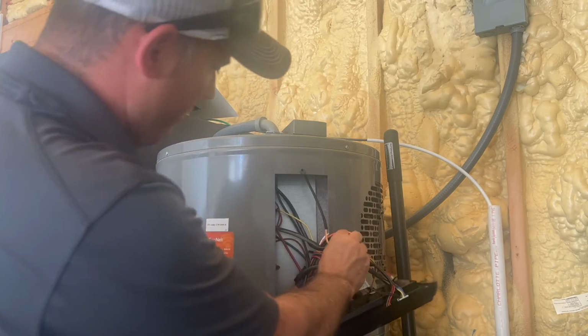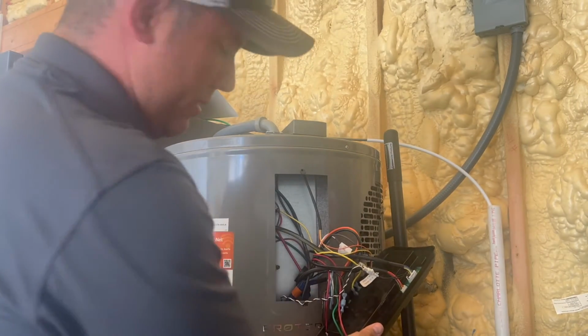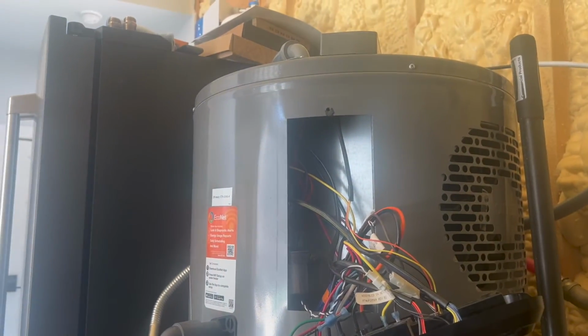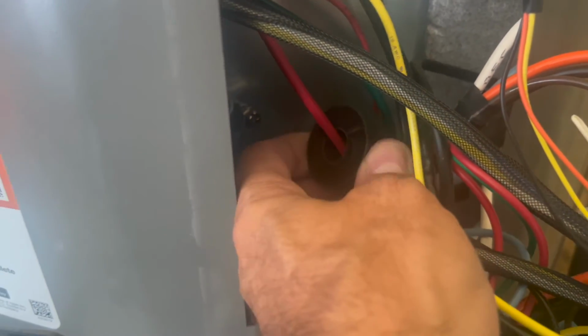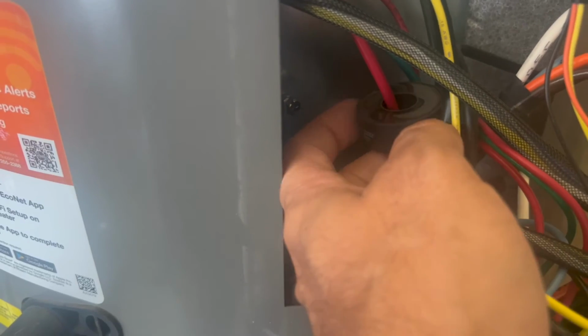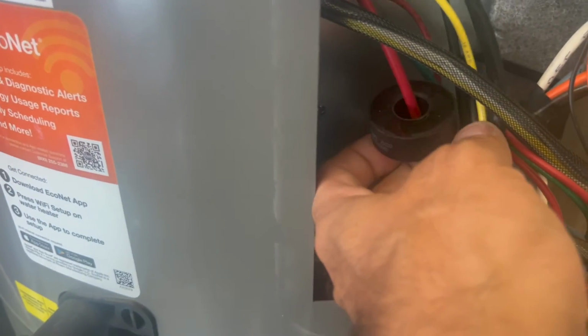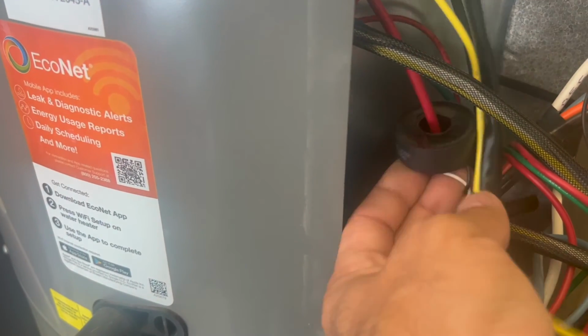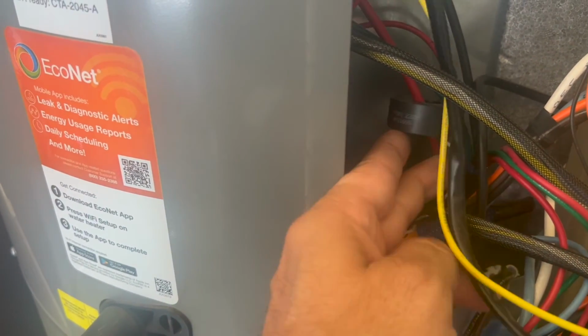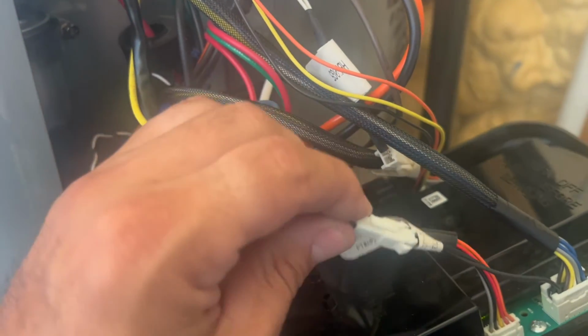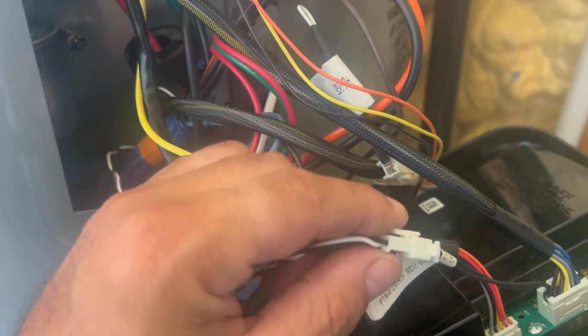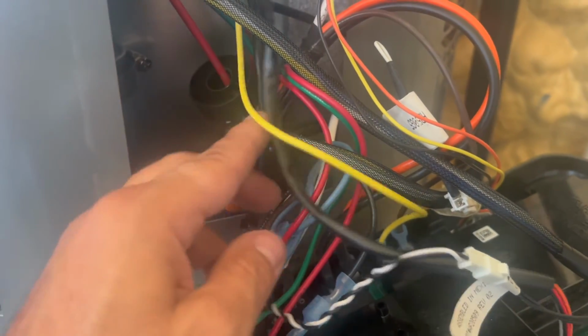Now, 2 key components right behind this user interface. It's going to be your current sensing transformer, your current sensor right here, little round donut around the red wire. It's a black and white wire coming off of that, and it connects to this plug here. This is where you're going to test from. You would disconnect this and ohm it out. You should get about 30 ohms on this resistor.